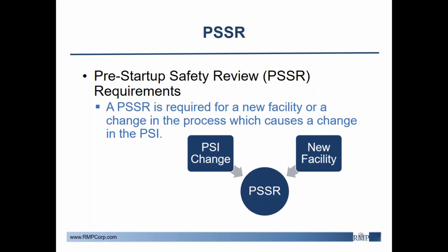So PSSR. A PSSR, known as a pre-startup safety review, is required for a new facility or when there's a change to the process that causes a change in the PSI. As Morgan touched on, MOCs are required when you have a change that's not a replacement in kind. So those two definitions are pretty similar. You rarely have a change that causes a change in your PSI that's not a replacement in kind, right? So a lot of times what facilities will do is combine these two elements together into one program. However, it's important to remember that PSSRs are their own element, especially with the change to regulations for refineries.